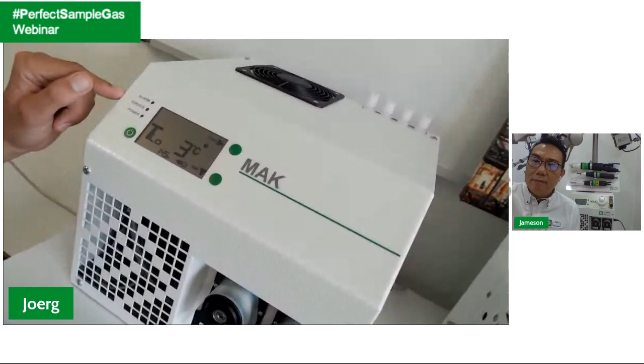So if you have the situation that the outlet dew point, meaning the temperature of the cooler, will have a problem, this information is shown on the display here. And at the same time, we will indicate this to the analyzer system, so that the sucking of the pump can be stopped.